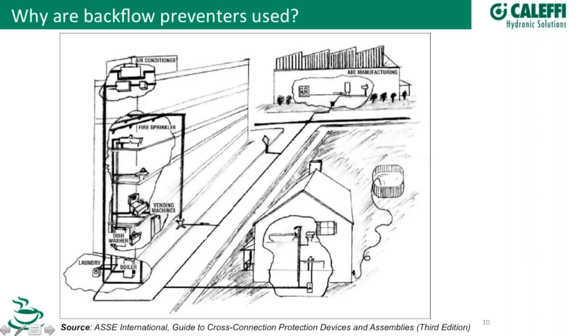On the left you see industrial. You're going to have a boiler that builds pressure, which could overcome system pressure. A lot of municipalities operate at 35 to 80 PSI. If that boiler can overcome system pressure, you're going to need varying degrees of backflow preventers. Per ASSE standard, if it builds over 30 pounds, you need a high hazard backflow preventer on the line that isolates that boiler — that would be the Caleffi 574 or ASSE 1013.